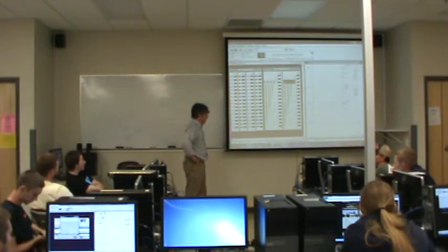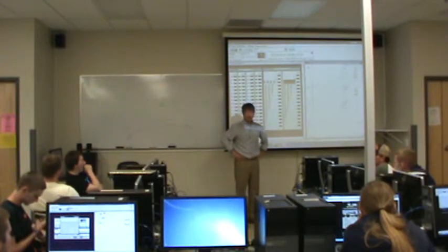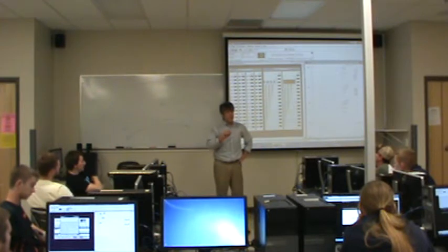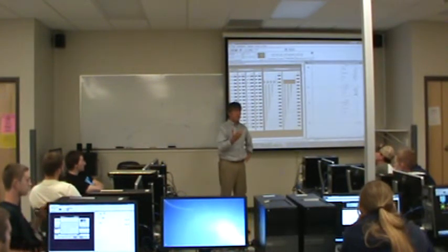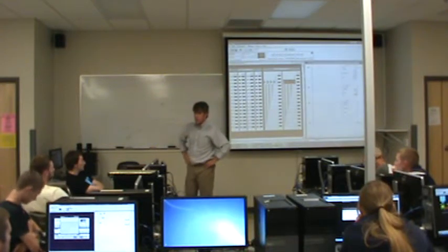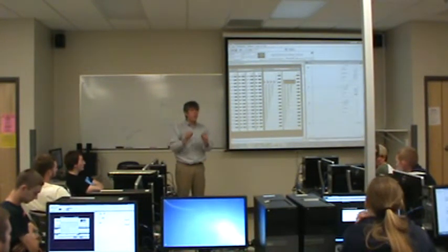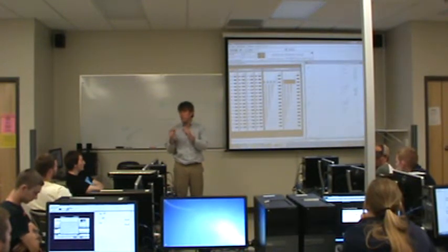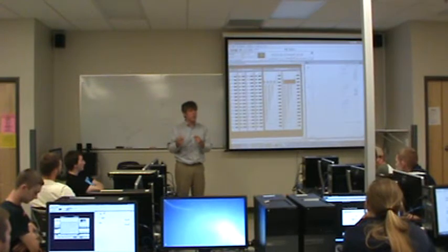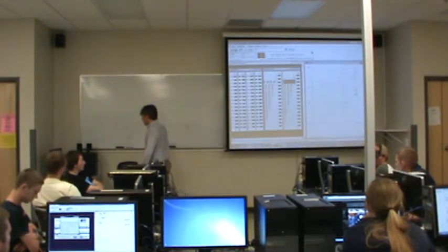Well, in this particular PLC, it does not deal with what's called floating point math. It can't save anything after the decimal place. So anything after the decimal place just gets thrown away and it keeps the integer portion of the result. Okay, so that's something that's important to know. And using a PLC or any microcontroller that has only integer math, when you're trying to do normal calculations, especially in integration or differentiation or anything like that, it's kind of an art in and of itself. Okay? But we're not going to discuss all that.